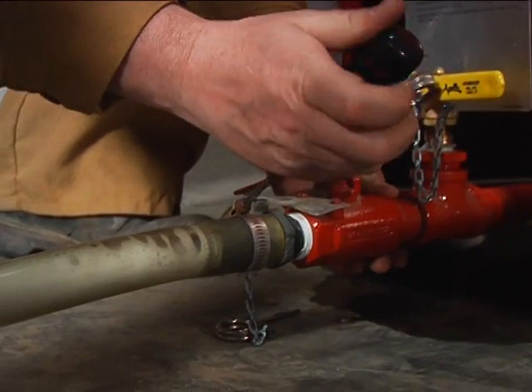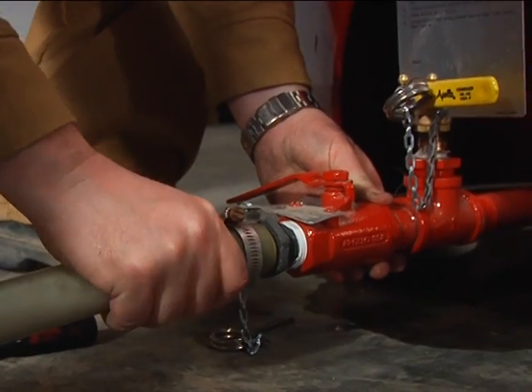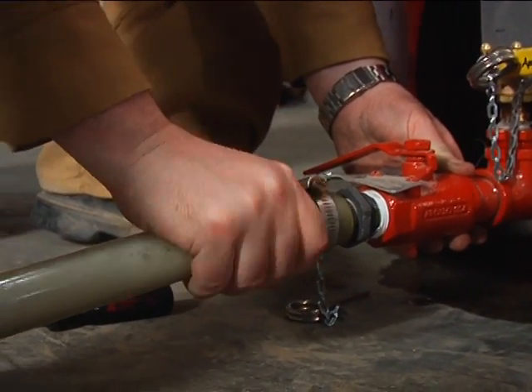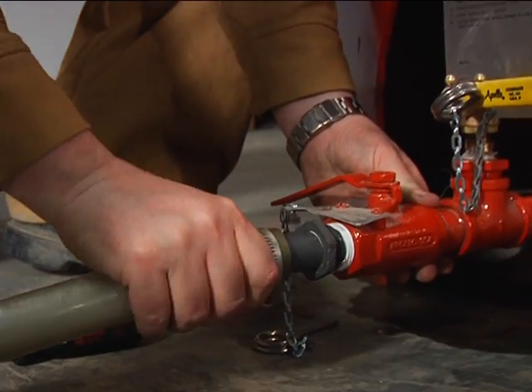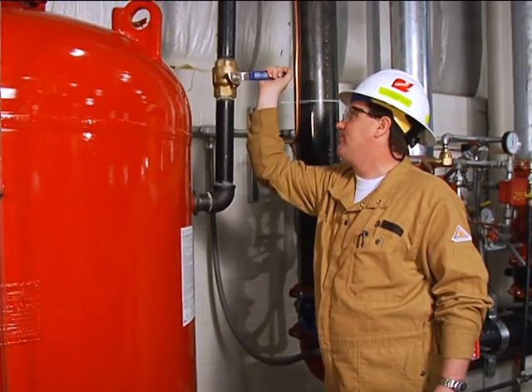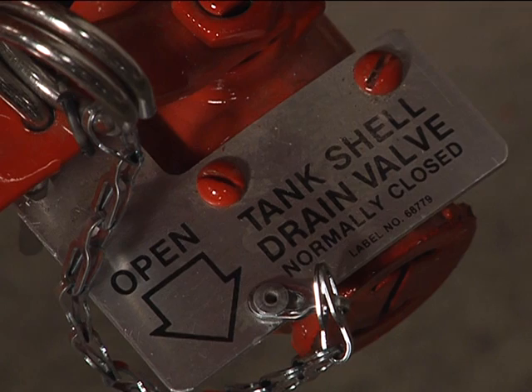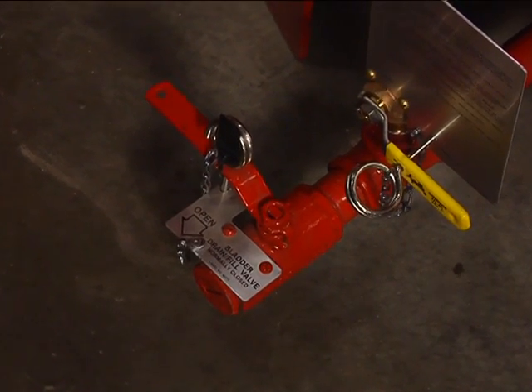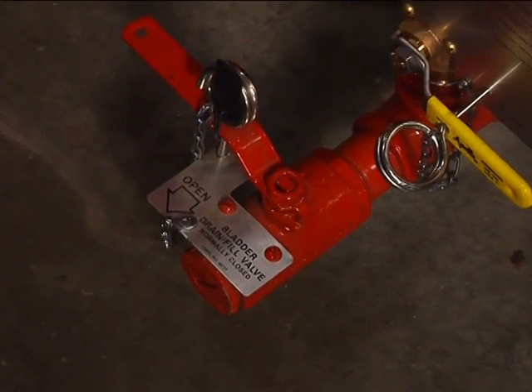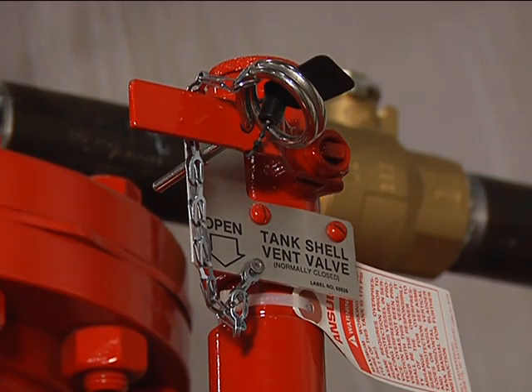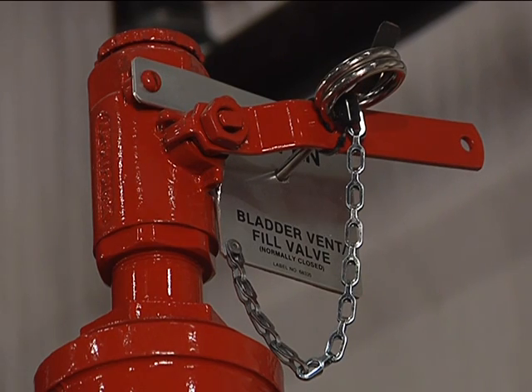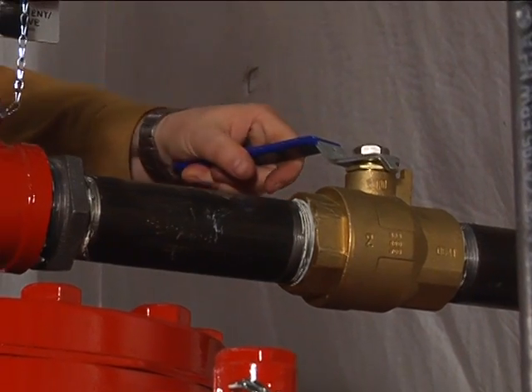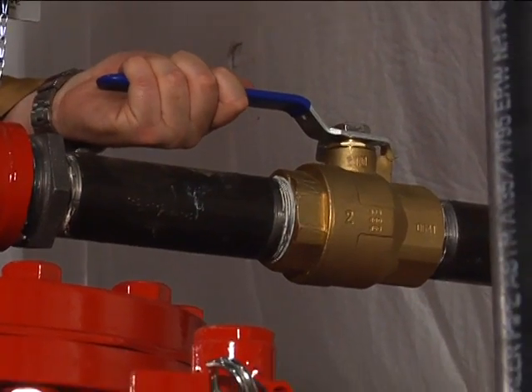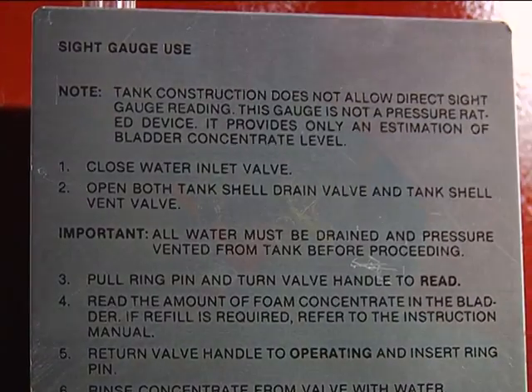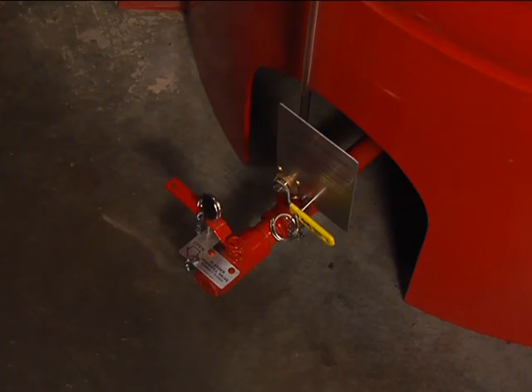Close the bladder drain fill valve and disconnect the concentrate pump. Return the bladder tank valve handles to the following operating positions. Water inlet valve, open. Tank shell drain valve, closed. Bladder drain fill valve, closed. Tank shell vent valve, closed. Bladder vent fill valve, closed. Concentrate isolation valve, normal operating position. If provided, sight gauge valve operating.